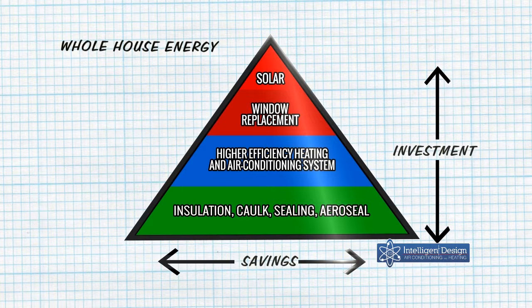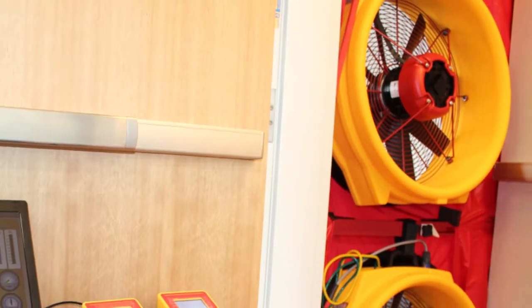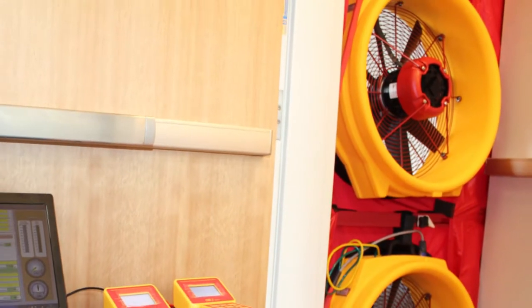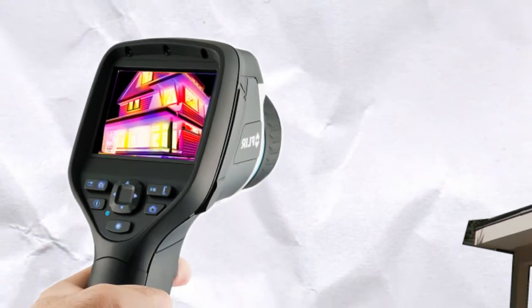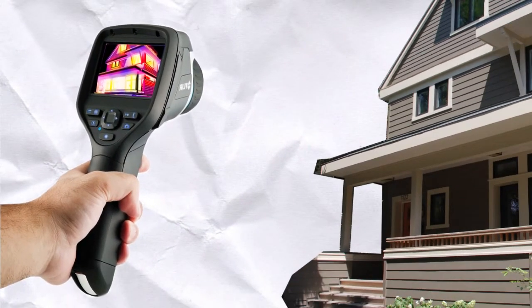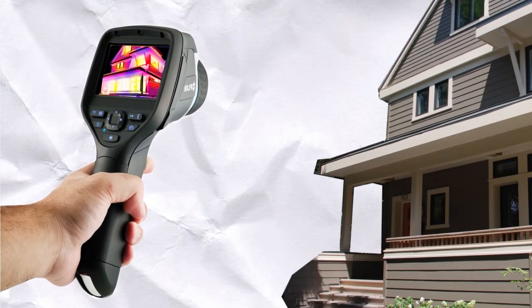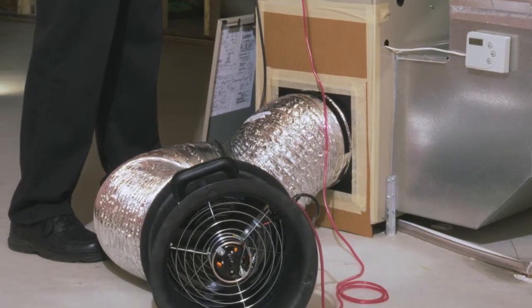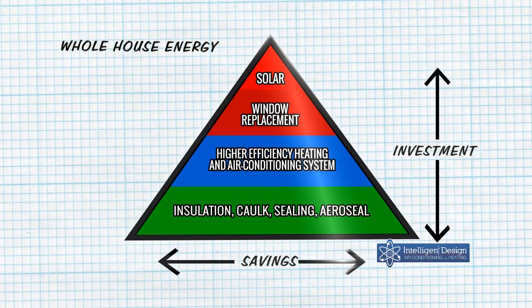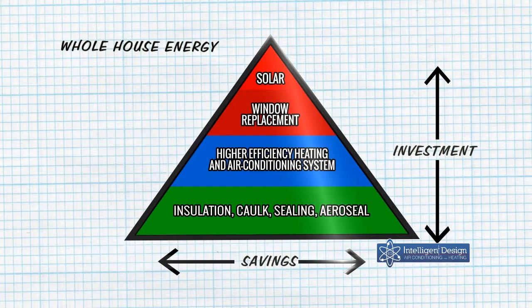What we do is come in and depressurize the house and test it for leaks. We look at the home with a thermal imaging camera to find missing insulation pockets, and we test the ductwork to see if it leaks. There's no sense in getting a 25 SEER top-of-the-line air conditioning and heating system if it's all blowing out into the cavity and attic spaces. Once we do those tests — those items are at the bottom of the triangle — then we move up.